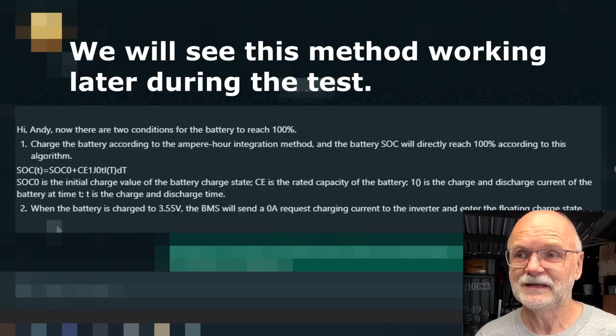He explained further that when the battery is charged to 3.55 volts, the BMS will send a 0 amp charging current request to the inverter and enter floating charge state. I think we don't actually have a float mode in version 3 of the Seplos BMS now.